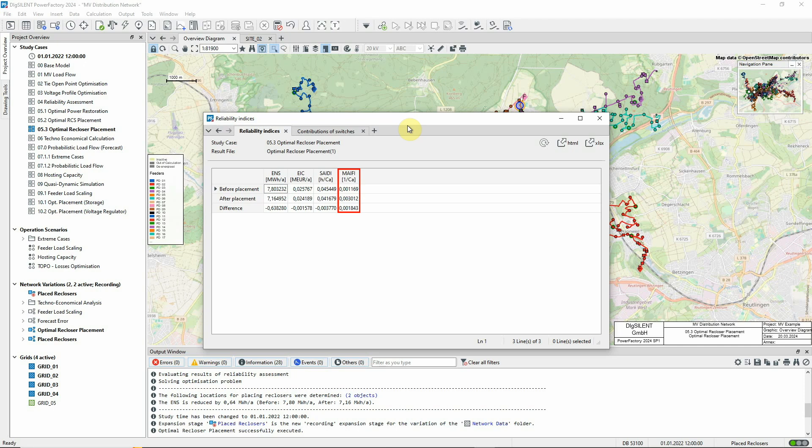This is partly because of failed attempts by the new reclosers to reclose on sustained faults, and partly because of successful reclosure after transient faults. In both cases, these events will result in momentary interruptions being registered.